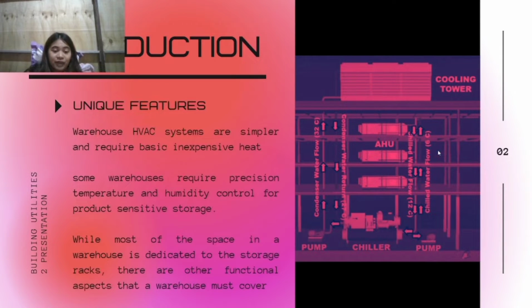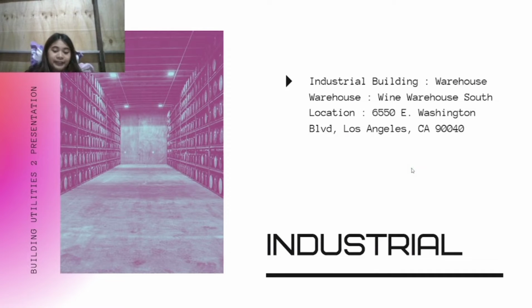So, some of the unique features of a warehouse HVAC system. First, warehouse HVAC systems are simpler and require basic and inexpensive heat, but as any structure would, warehouses bring their own set of design challenges. Second, some warehouses require precision temperature and humidity control for product-sensitive storage. Third, while most of the space in a warehouse is dedicated to the storage racks, there are other functional aspects that a warehouse must cover. Some warehouses need to maintain low temperature for products like wine, requiring cold storage, while humidity can be an issue for others. So for our research, we chose to dissect the HVAC system of an industrial building type, which is a warehouse. Specifically, the Wine Warehouse, Southern California, located at Los Angeles, California.